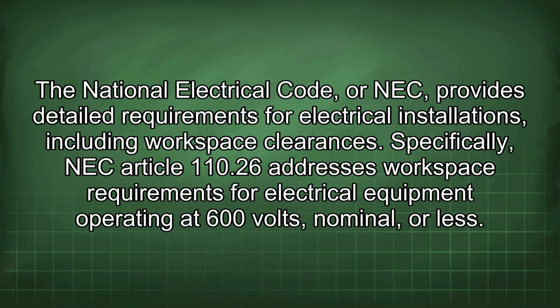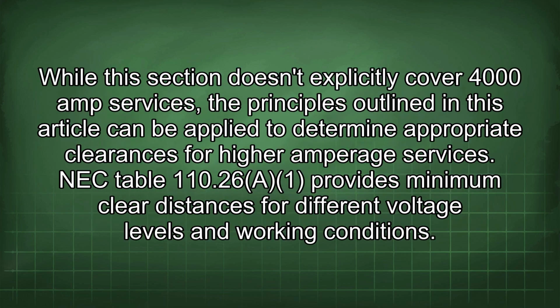The National Electrical Code, or NEC, provides detailed requirements for electrical installations, including workspace clearances. Specifically, NEC Article 110.26 addresses workspace requirements for electrical equipment operating at 600 volts, nominal or less. While this section doesn't explicitly cover 4000 amp services, the principles outlined in this article can be applied to determine appropriate clearances for high amperage services.